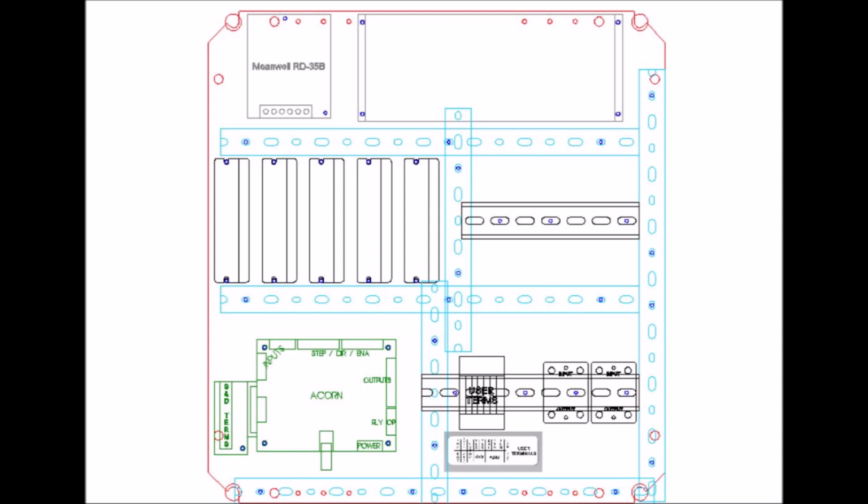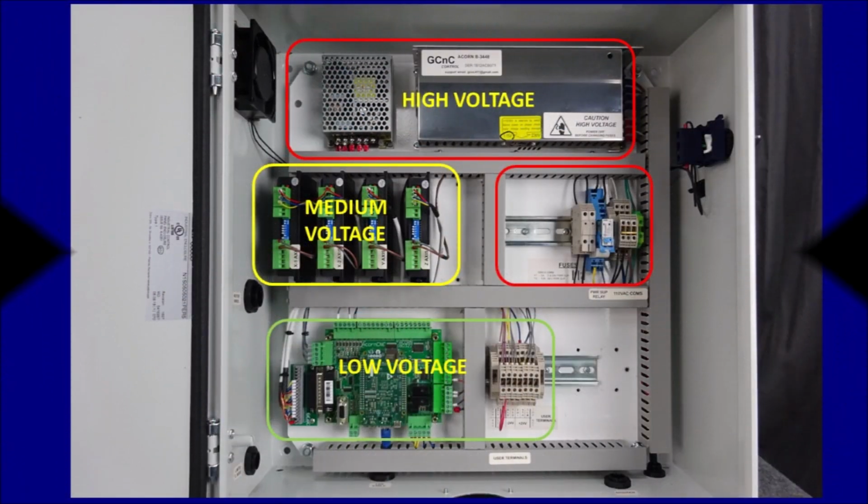It seldom works this well, even on the first, maybe even the second or the third time. But if you spend some time to do this and get it organized the way you want, if you have wire duct like I use, or DIN rail, or just need space for wiring or mounting other components, you want to make sure you have that in. Lay those out on a sheet of plywood and use that to determine the size of boxes.